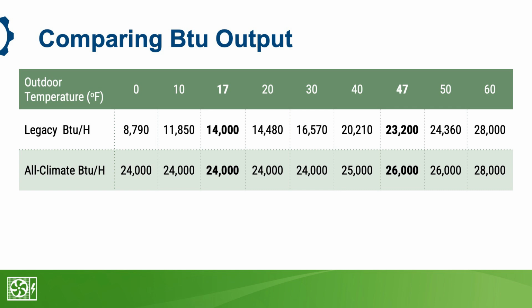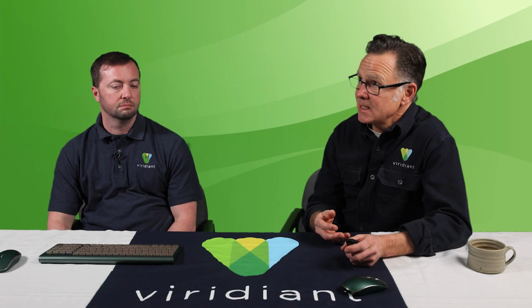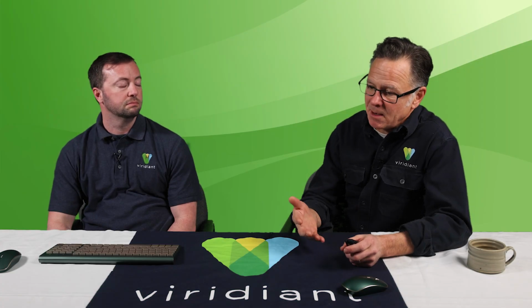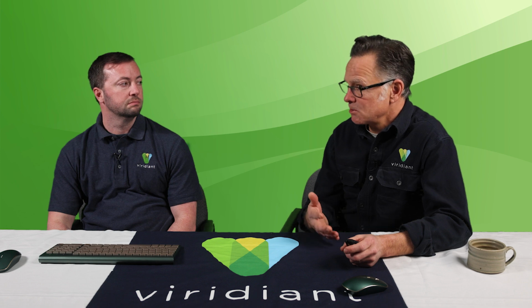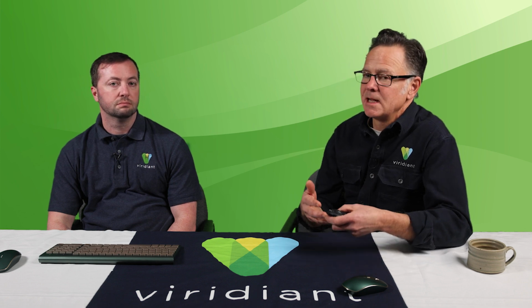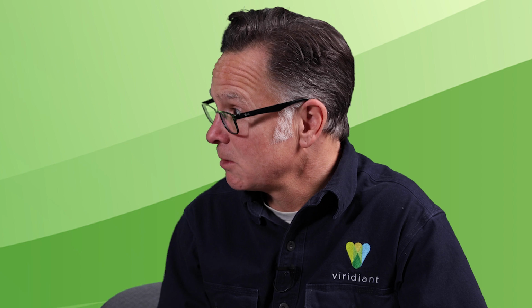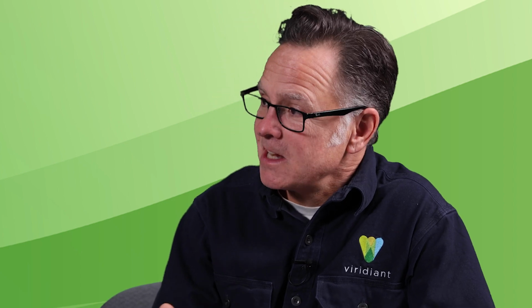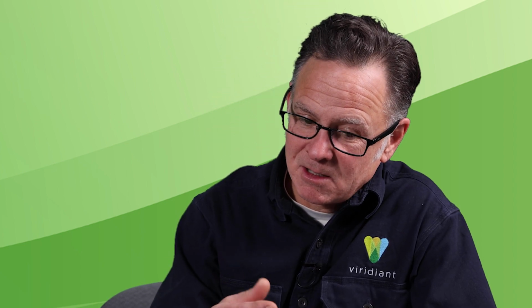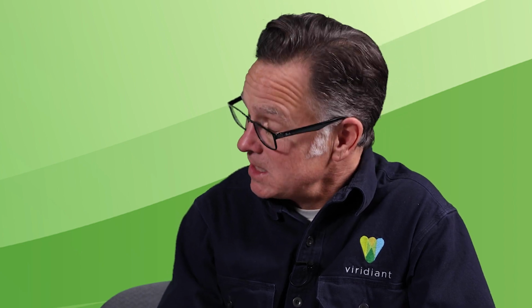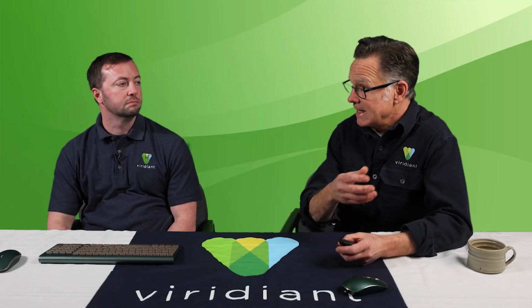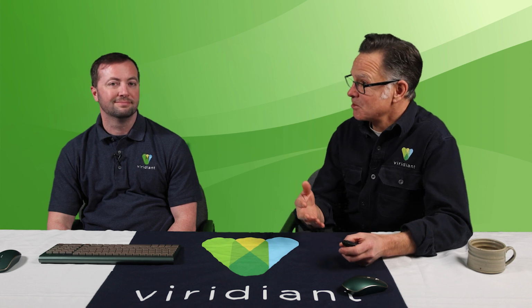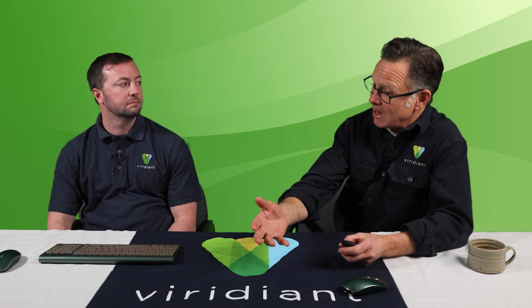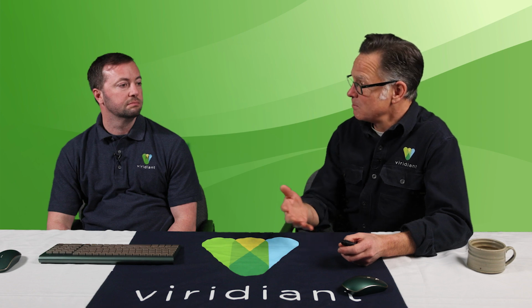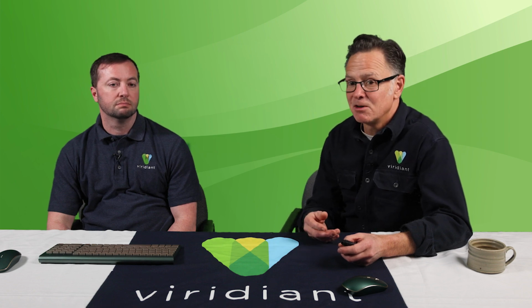So here we're going to talk about the actual heating and cooling potential for the equipment. And I think this is where there's a real breakdown between popular understanding of heat pumps and what they're supposed to do and what an installer needs to communicate when they're providing equipment for the home. The device is created to deliver a certain number of BTUs of heating and BTUs of cooling. And it's printed right there on the manual. So then it's just a matter of determining how many units of heat or cool the home needs, and will this piece of equipment deliver it?